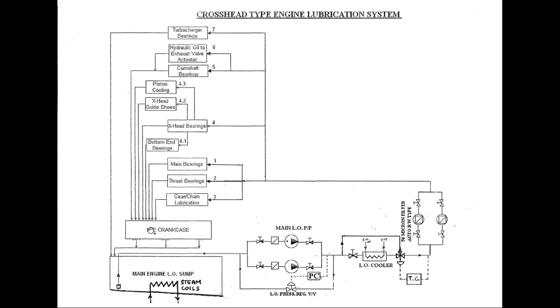Crosshead oil is also supplied upward for piston cooling through an outer annular pipe located inside the piston rod. After cooling the piston, the oil drains down through the inner annular pipe in the piston rod and comes out of a drain pipe connected to the crosshead through a temperature side glass, temperature sensor, and no-flow alarm. If piston cooling is ineffective, high temperature will be noticed at the oil outlet; if there is failure of lube oil flow, a no-flow alarm will be given. The watch keeper can also visually confirm regular flow of piston cooling oil at the outlet.